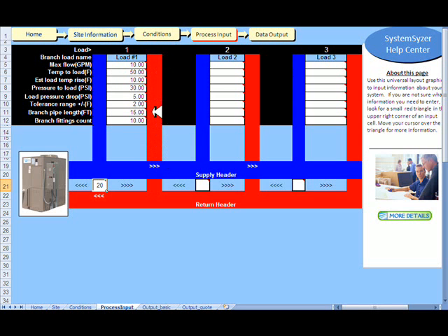to put that in. And then the branch fittings count, and this is a little difficult to get to, but if you look at the hint box here, we recommend a ballpark to figure on one fitting for every foot of pipe, and that's probably more than you'll need, but we have to use that to calculate your pressure drop, right?